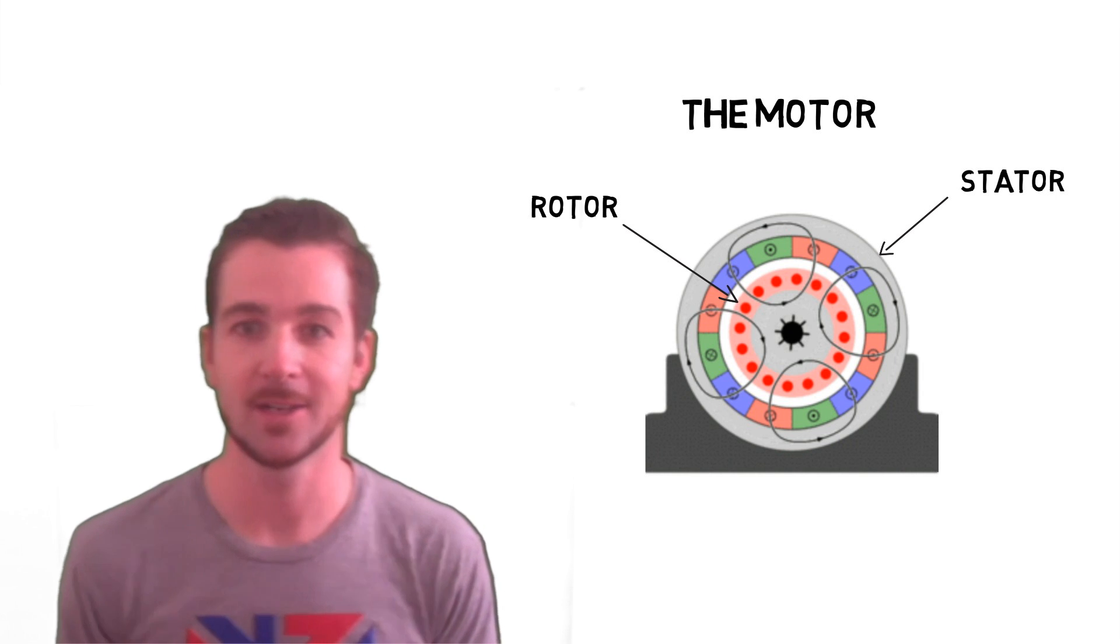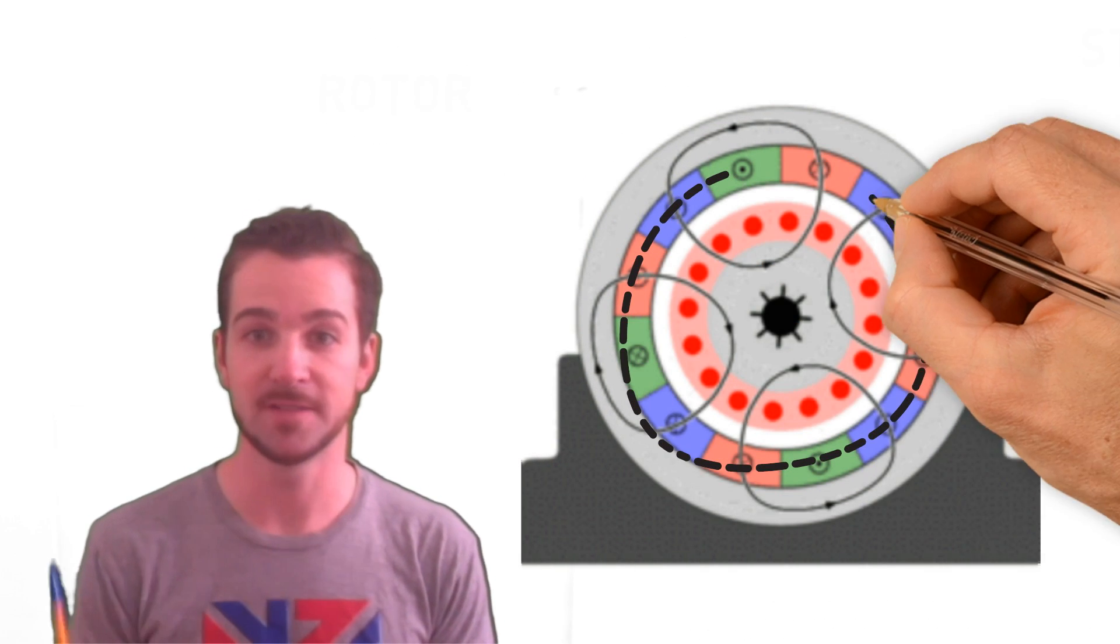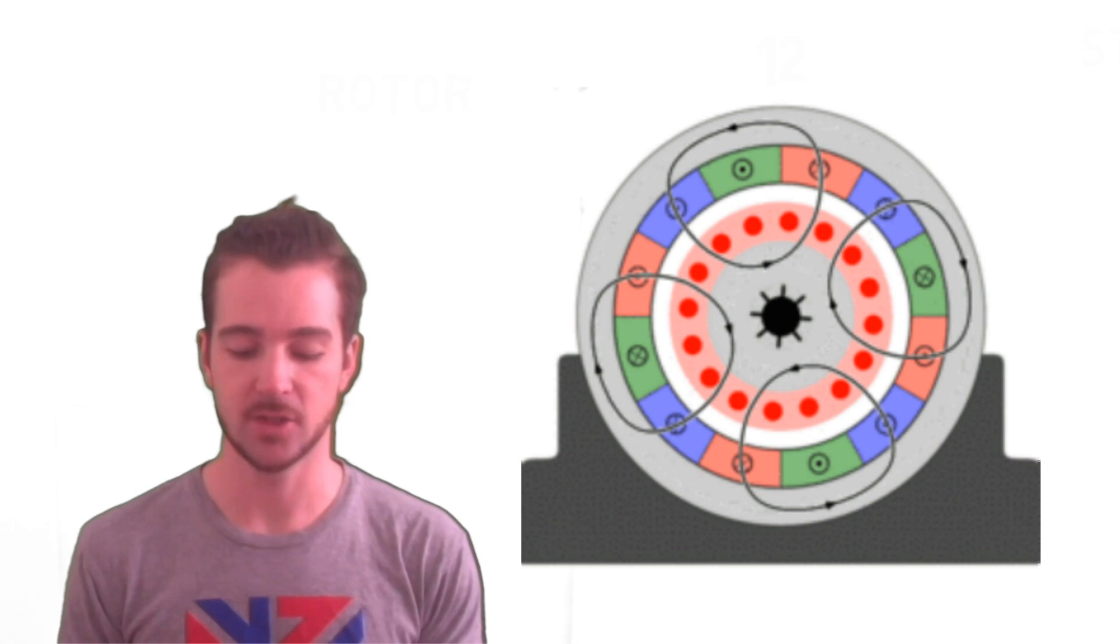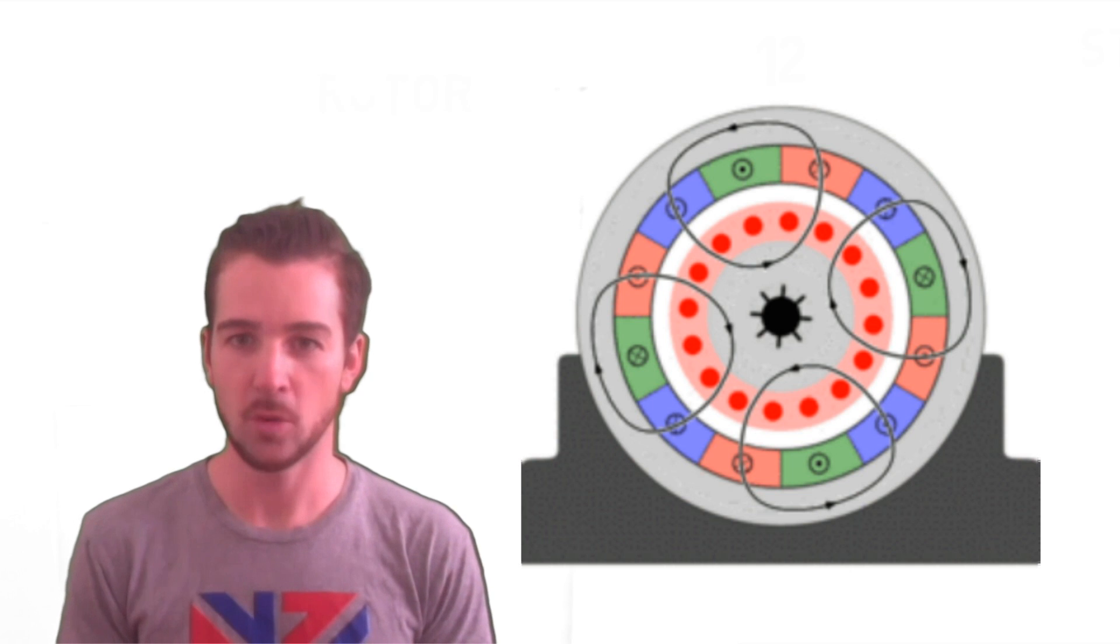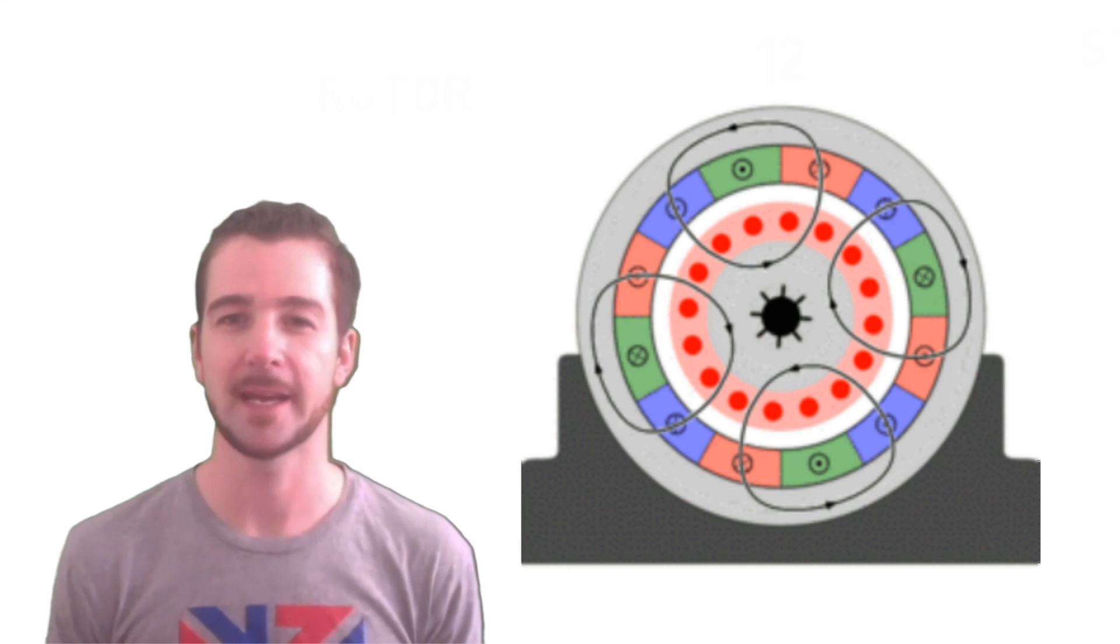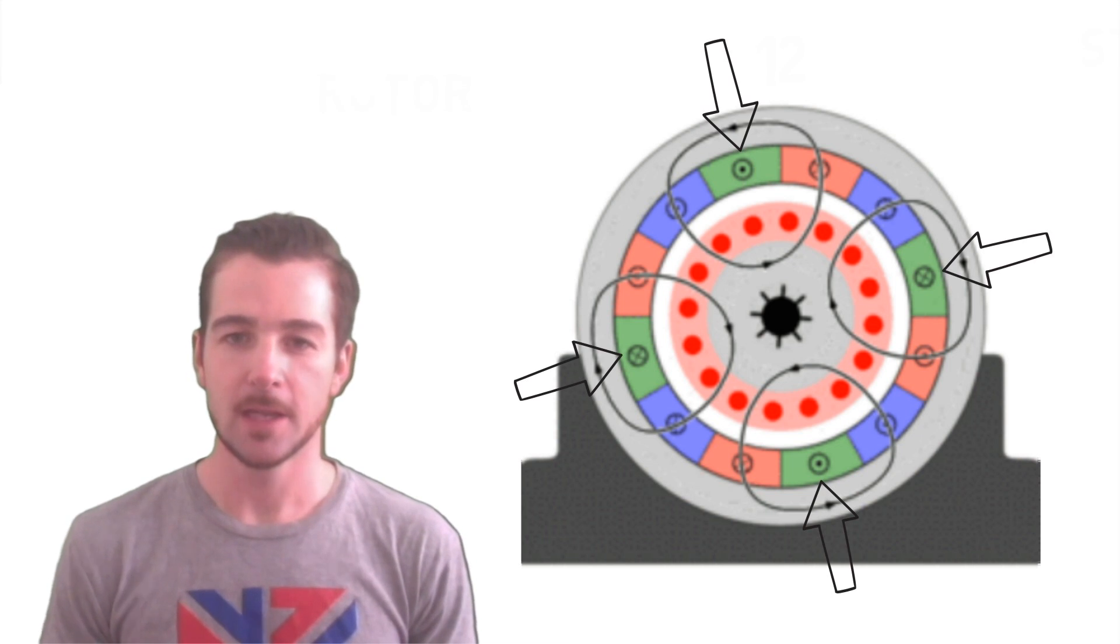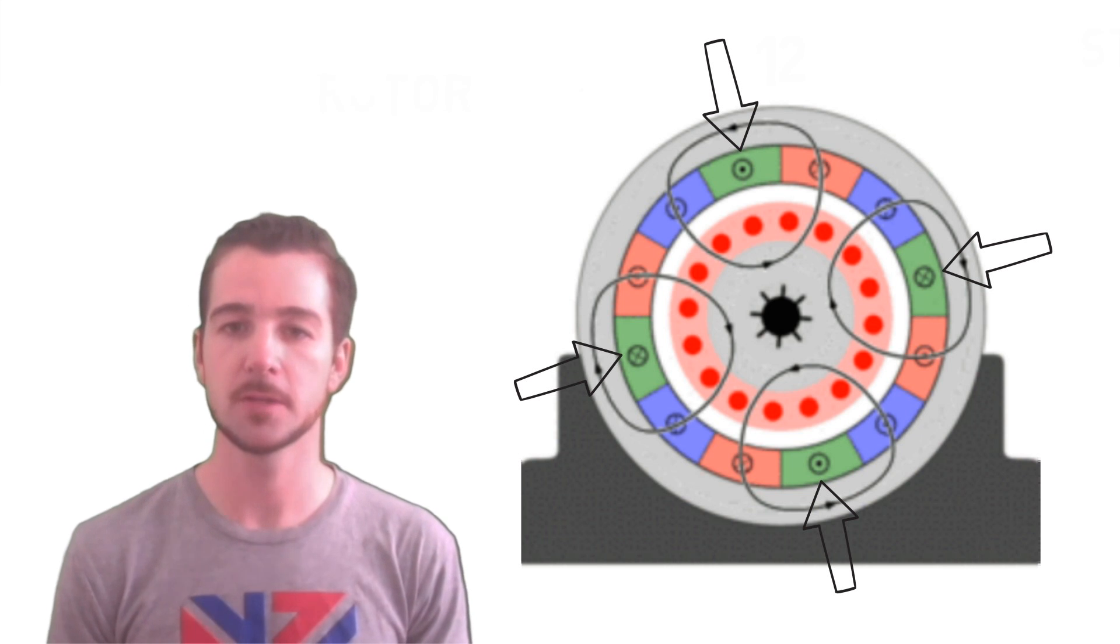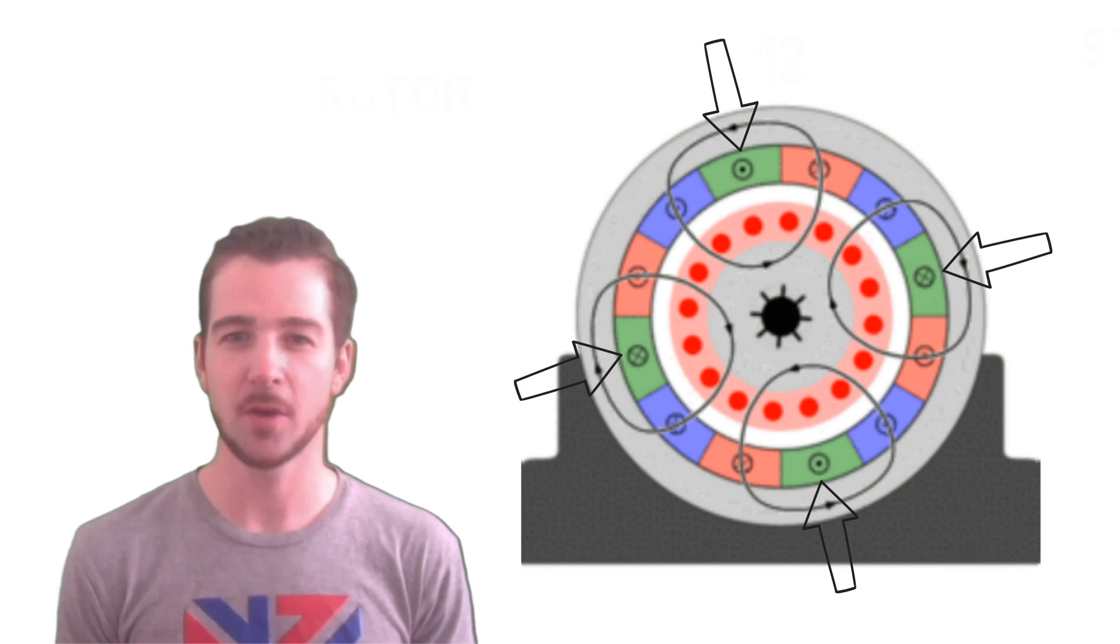All right, let's have a closer look at the stator. So, you can see the stator is divided into 12 segments. Each one of these segments has a color. There's green, red, and blue, and all the greens are connected, all the reds are connected, and all the blues are connected. What do I mean by connected? Well, let's take the green for example. These four parts of the green, they're called poles, these four poles, are all made of one big loop of wire.